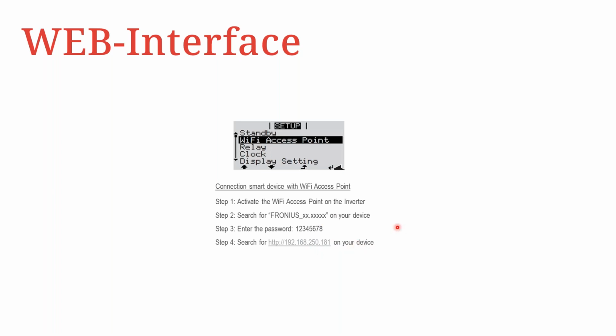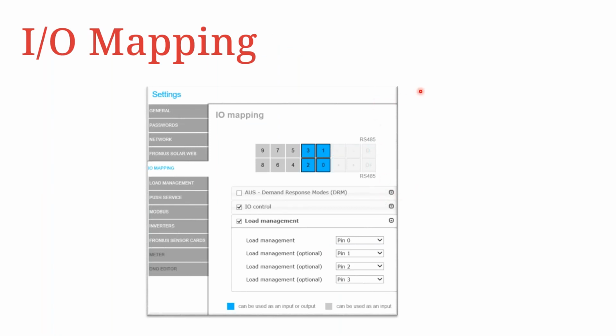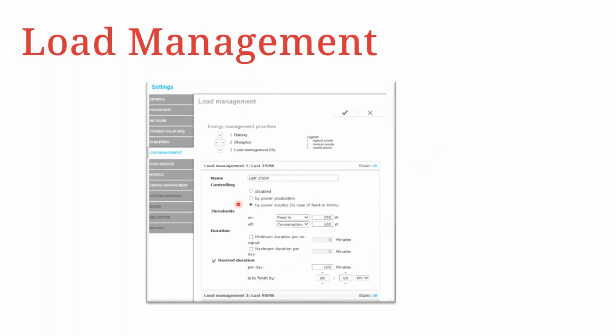Once you have connected to the web user interface of the inverter, if it's a Data Manager, then you'd go to the IO mapping section, and this IO mapping would then allow you to activate any of these outputs. So we have output 0 up to 3 here, and then you can see here the descriptions. All of these can be used for load management. Once you activate, you can assign the thresholds for activation for that particular IO, depending on the portion of excess energy that is available. So in detail, for this example, we have a load management for IO1, where we are saying that for the last 250 watts, this is the operation behavior that we want.